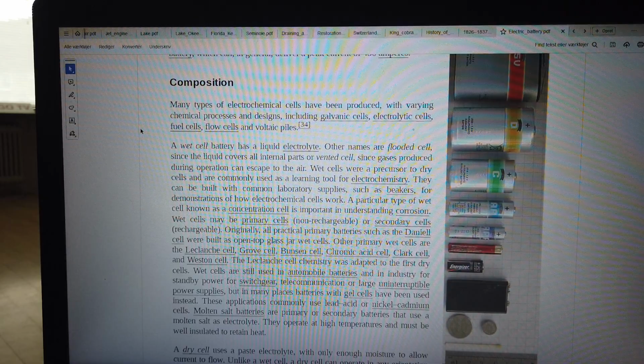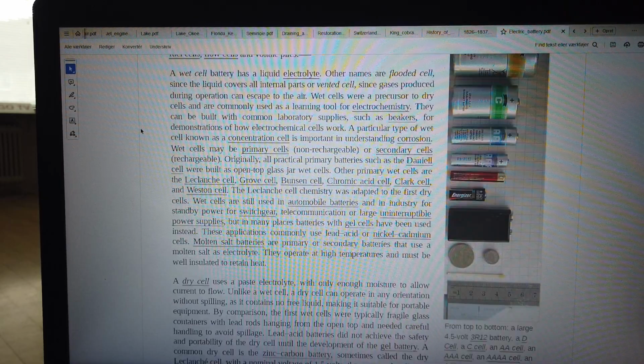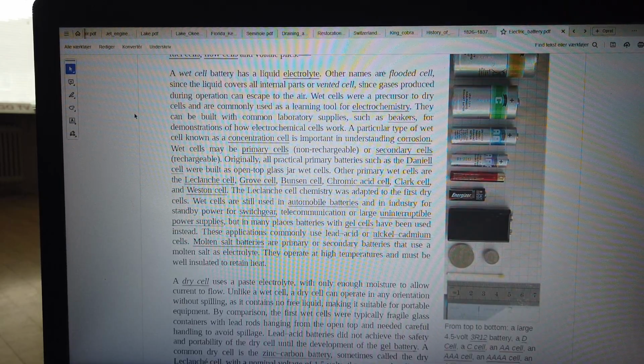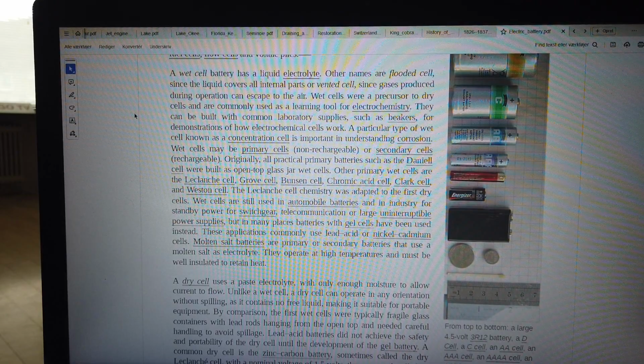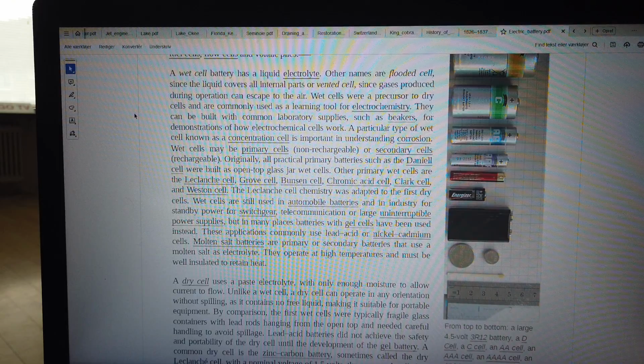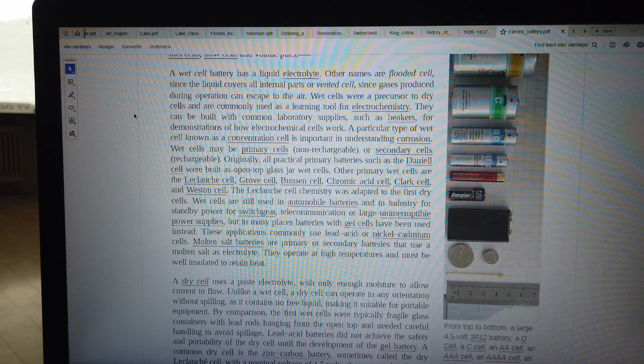A wet cell battery has a liquid electrolyte. Other names are flooded cell, since the liquid covers all internal parts, or vented cell, since gases produced during operation can escape to the air.